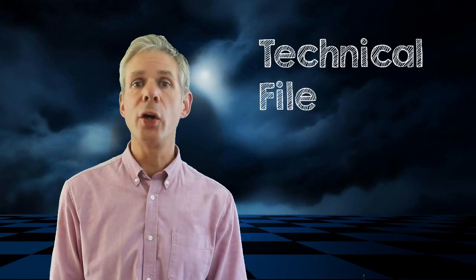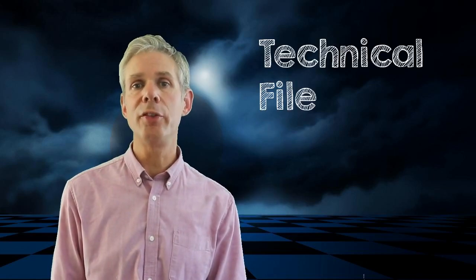2. You need a comprehensive technical documentation file for your device. For everything above a Class 1 device, that also means testing reports, clinical evaluation and risk management documents, labelling, and a unique device identifier. Class 1 devices have lower documentation needs, but remember they're still very important. All classes of devices must demonstrate how they meet the general safety and performance requirements in Annex 1 of the MDR.